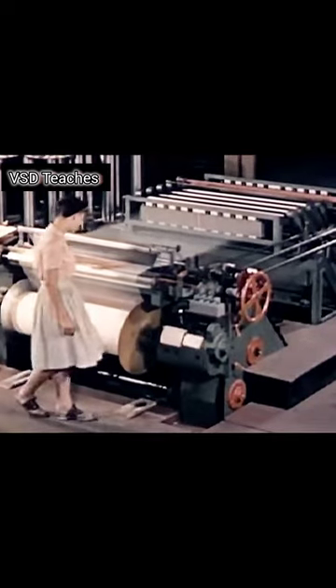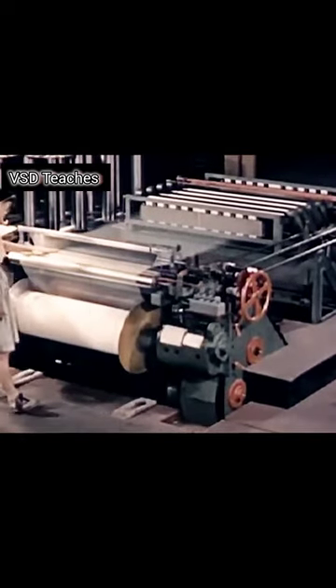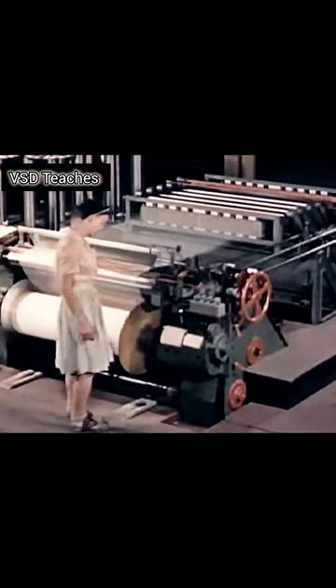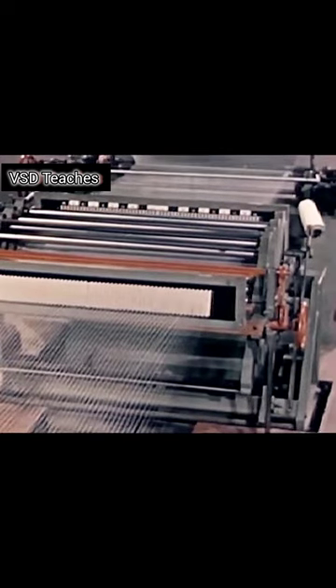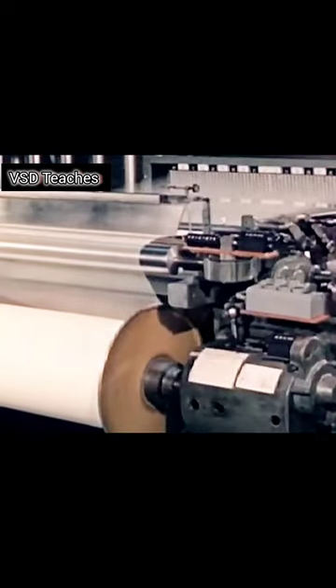A new warper drive is another example of the trend to higher controlled speeds. This drive will handle yarns of any fiber or filament, no matter how delicate they are, because speed is controlled electronically. Yarn tension is uniform, for yarn speed is kept constant within 0.5% throughout the doff as the beam diameter increases. Yarn breaks are headaches in any man's mill. Constant tension reduces them, so there aren't so many stoppages.